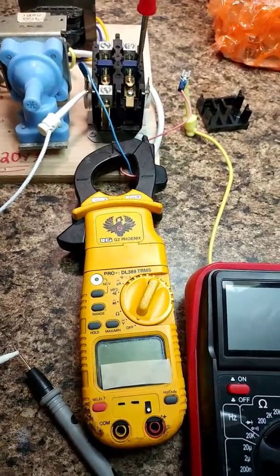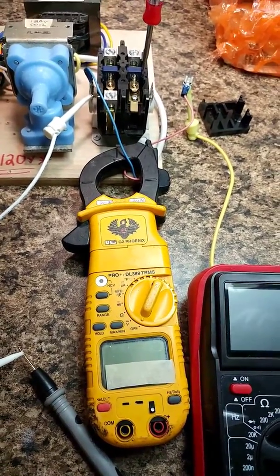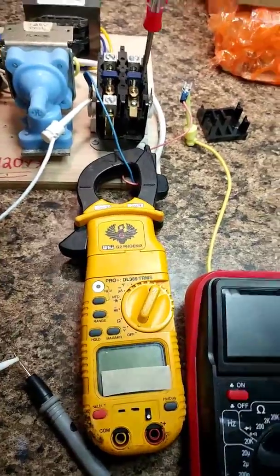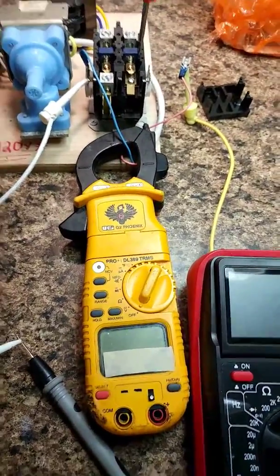And you'll usually notice it because you'll see a heavier spark. But if you've got your amp probe on it, you'll notice it. And then you can just kind of go to that circuit and isolate it.